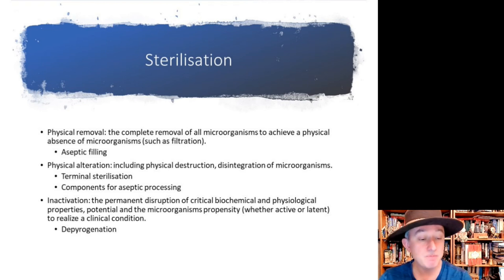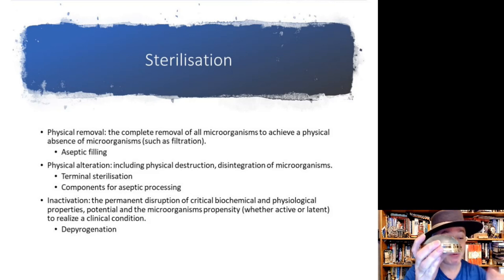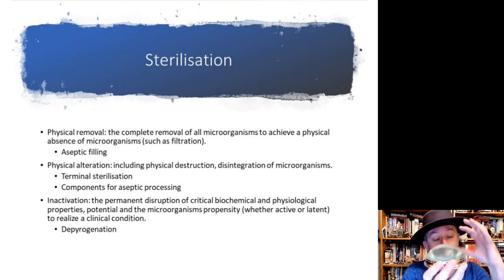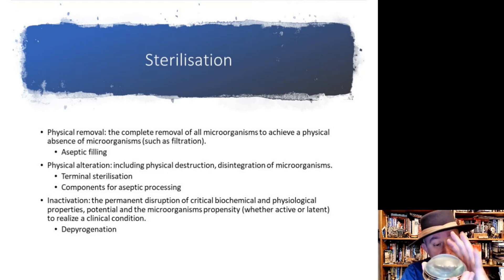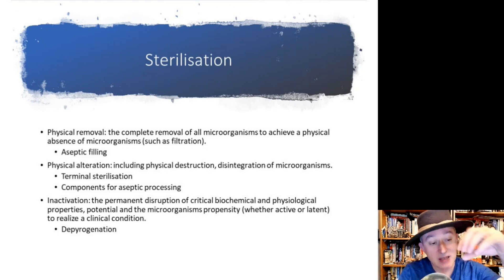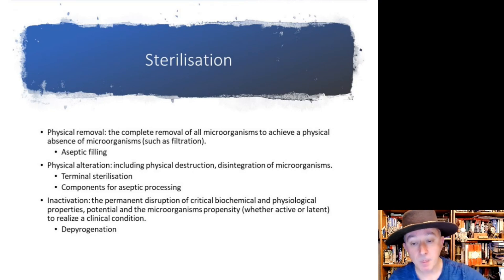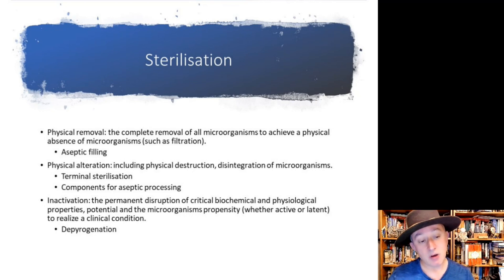With aseptic filling, we can't sterilize the medicine in its final container. We have to make sure all the parts going to create the medicine are themselves sterile — sterile vessels, sterile filters, depyrogenated vials, sterile stoppers. But if something were to fall in during the act of dispensing the medicine, we would have a serious problem.